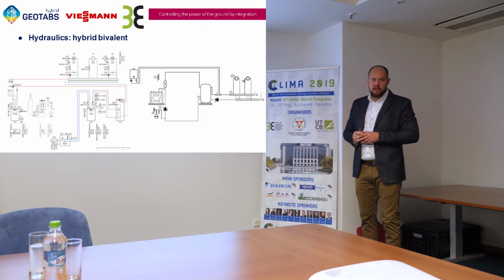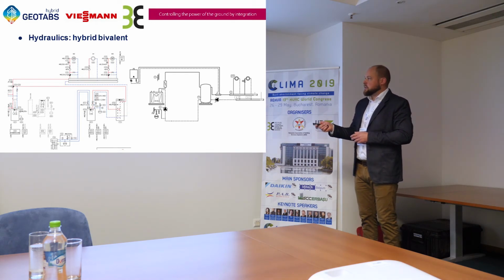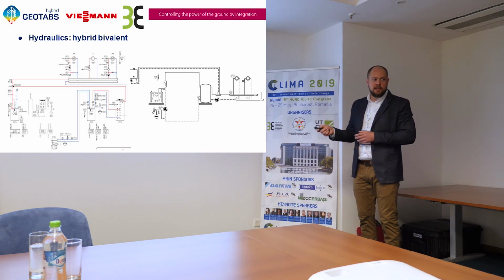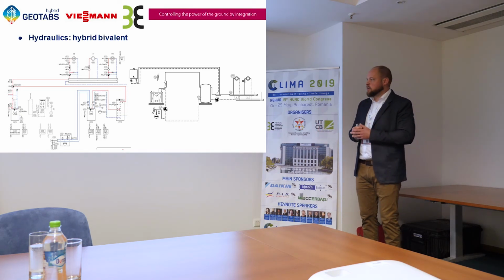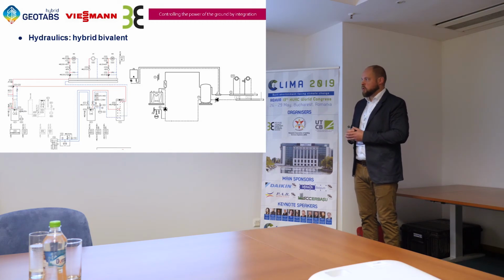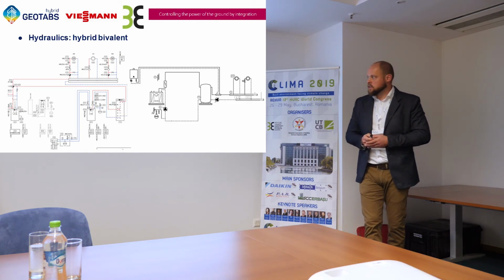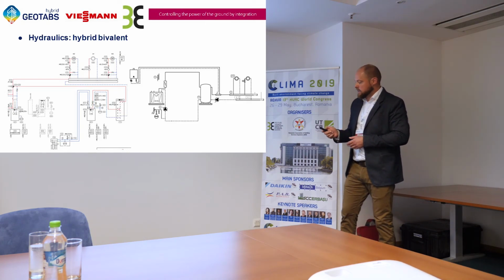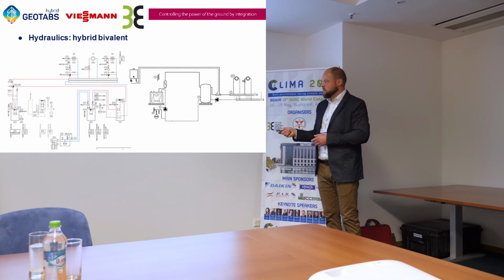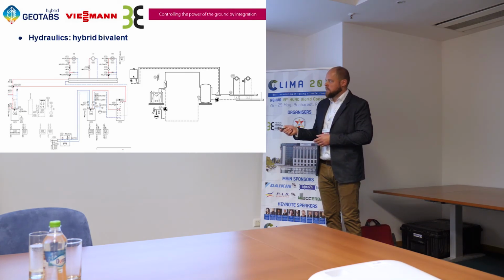The risk we have here is when the gas boiler begins to work, is that the gas boiler will heat the total buffer tank. And then the heat pump will also think that it has nothing to do, and the heat pump won't start anymore. So we have another type of schematic that we use, and that is actually the heat pump is connected to the buffer tank, and after the buffer tank we have a mixing valve that mixes heat out of the gas boiler when needed.